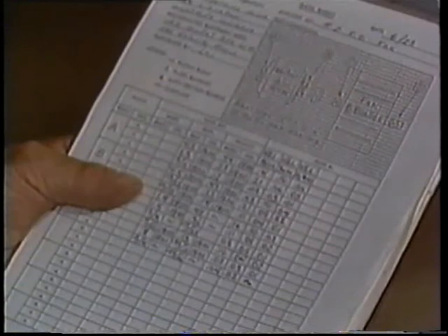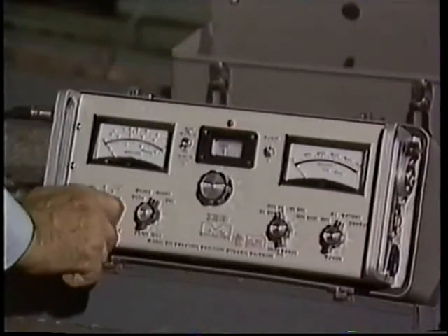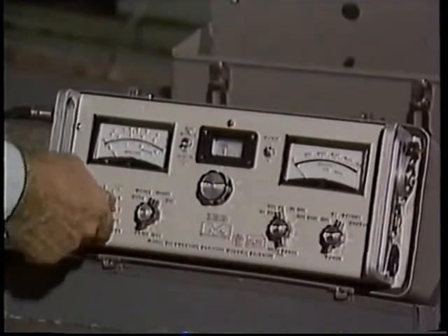You can check that you've located all the significant frequencies by comparing the filter out vibration amplitude with the sum of the filtered vibration amplitudes. If you've located all the significant frequencies, the two totals should be the same. For instance, say you had a filter out reading of 0.5 inches per second, and your first filtered reading was 0.3 inches per second. Since the sum of your filtered readings should be equal to or greater than the filter out, you need to keep scanning through the frequency ranges until you locate all the vibration.